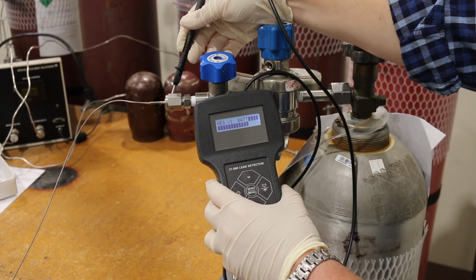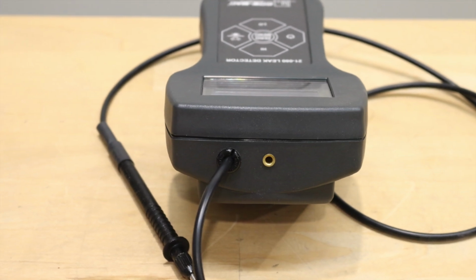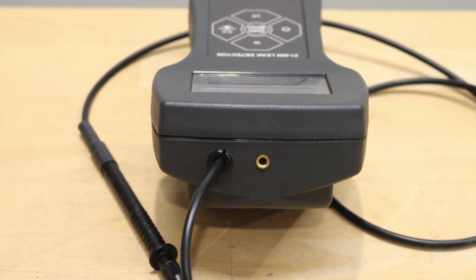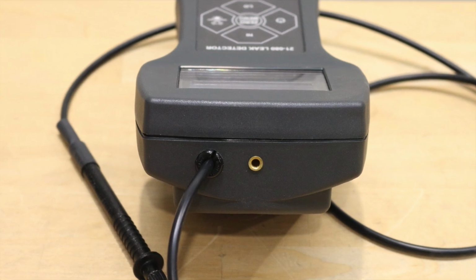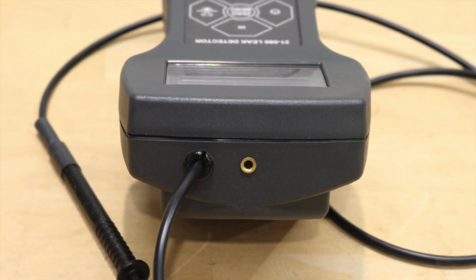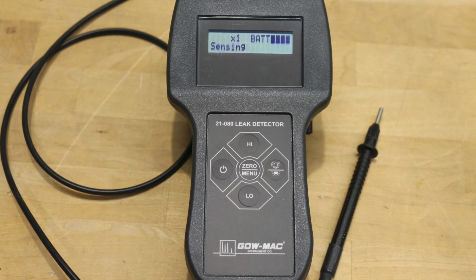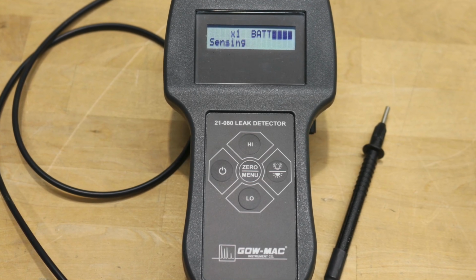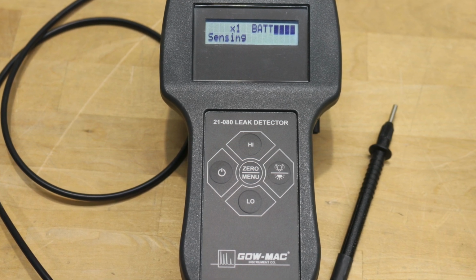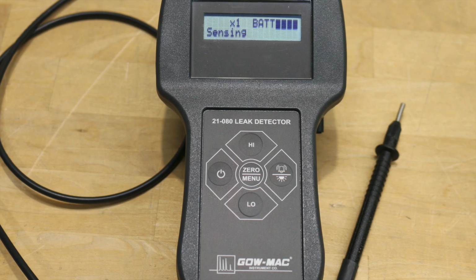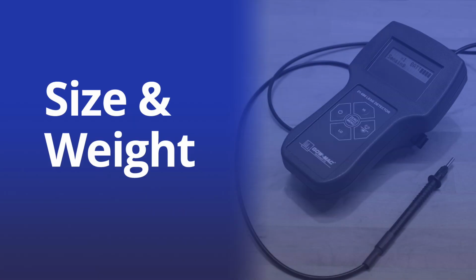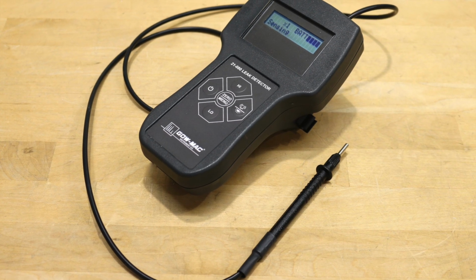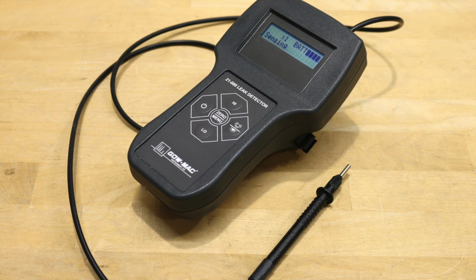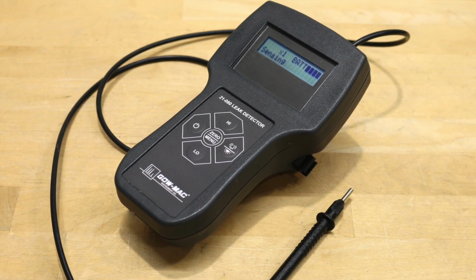Battery life. The 21080 is powered by a rechargeable nickel metal hydride battery that ensures a long run time and life cycle. A multi-stage, high-efficiency charging circuit keeps dissipation at minimum, allowing low drift operation after charging. To achieve the highest sensitivity for extremely small leaks, the instrument should be disconnected from the charger and turned on for 5 to 10 minutes to allow thermal equilibrium to be reached. Size and weight. Excluding the measuring probe, the 21080 measures 4.1 by 3 by 7.5 inches. This compact leak detector weighs in at only 1.2 pounds.